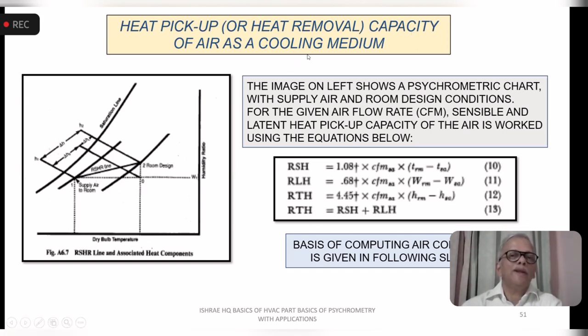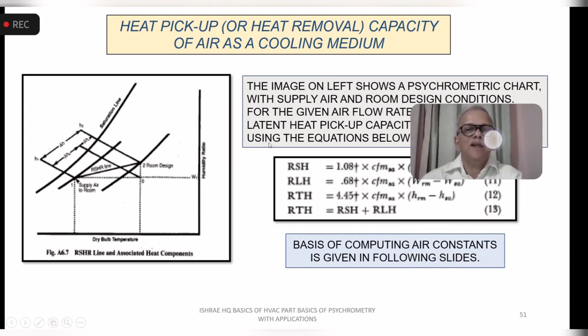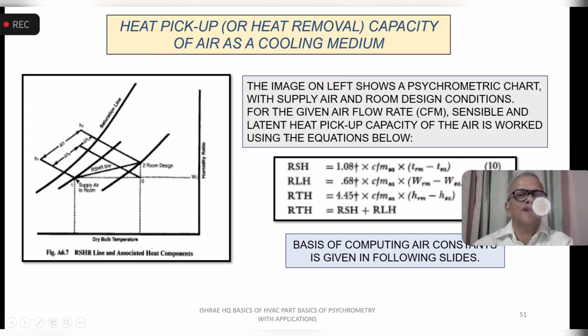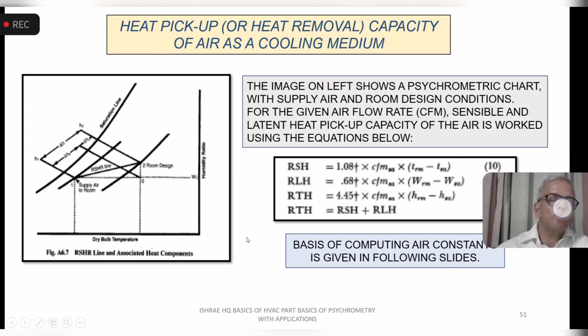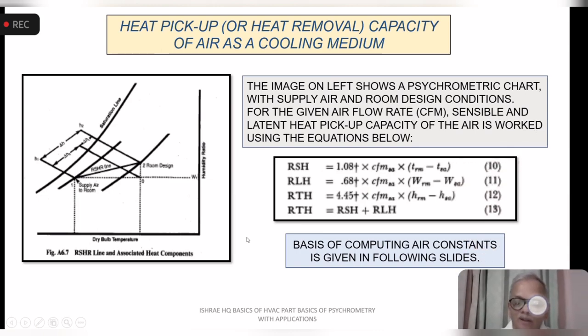Air is a cooling medium, as we said. The image on the left is showing the psychrometric chart with the supply air and room design conditions. For the given airflow rate or CFM, the sensible and latent heat pickup capacity of the air is worked out. Now I am going the opposite way.